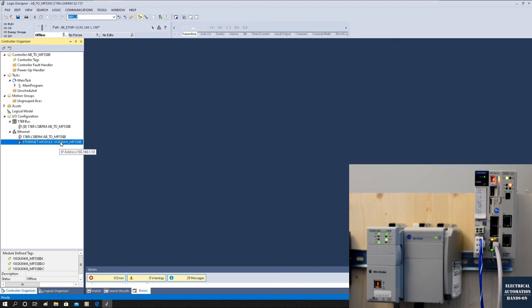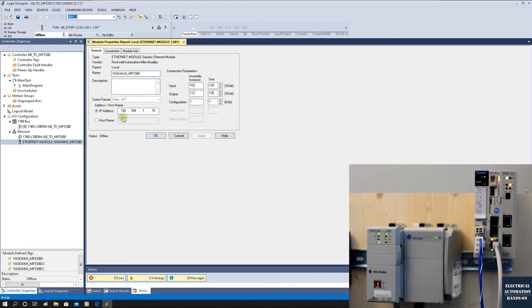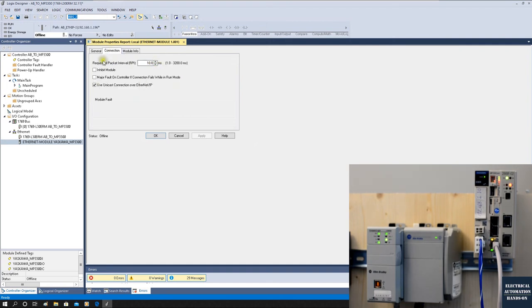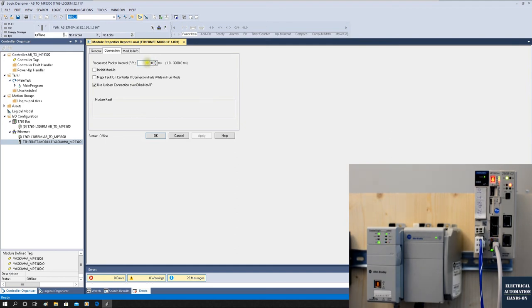We've set up the connection. Double-click to review the settings we just configured. Look at the RPI time — 10 milliseconds. We can leave this as default. For Ethernet IP communication, the communication cycle should generally be kept above 10 milliseconds. If you need lower than 10 milliseconds, be careful — some devices cannot respond that fast. I recommend using Unicast for point-to-point communication. Leave the RPI at 10 milliseconds.